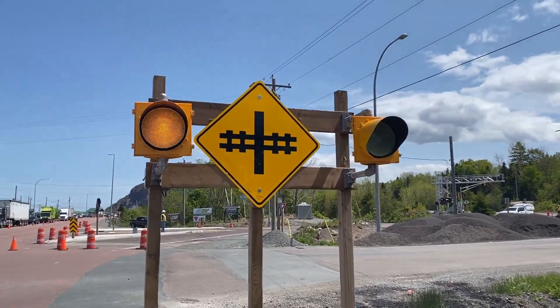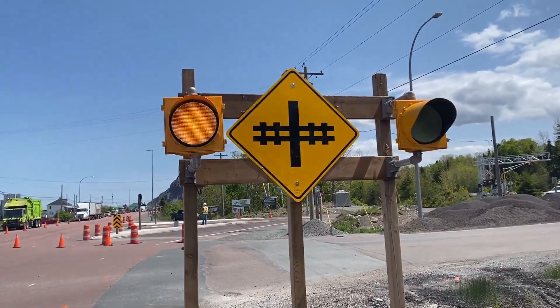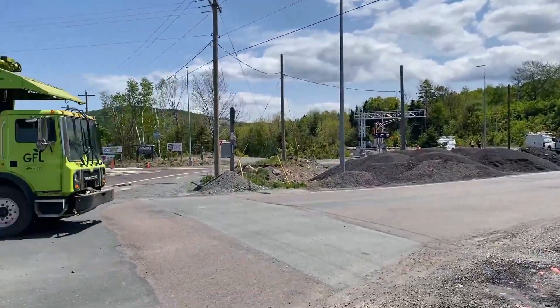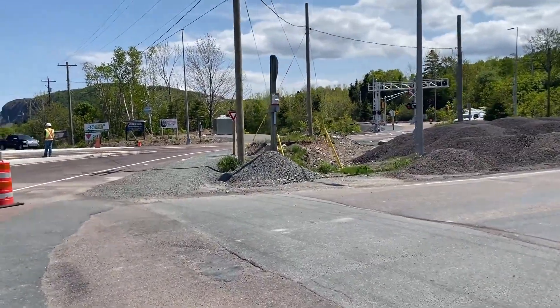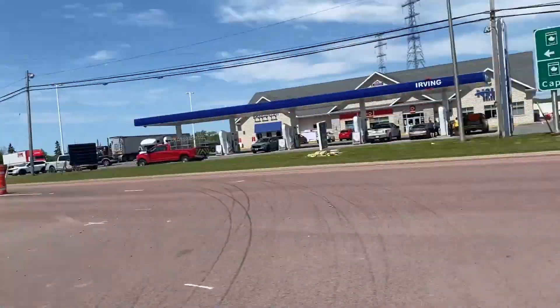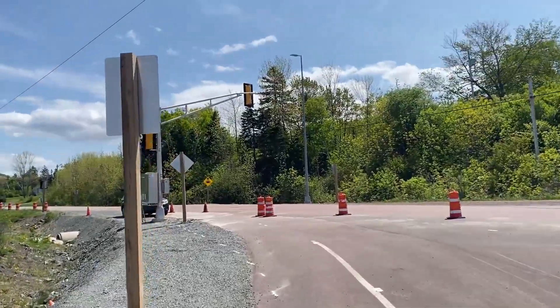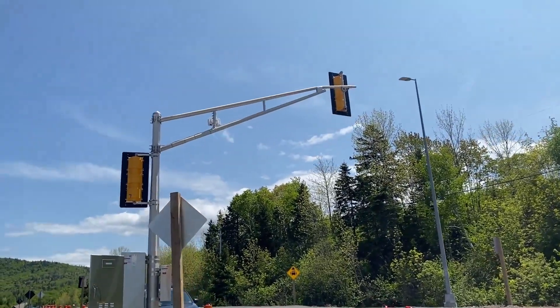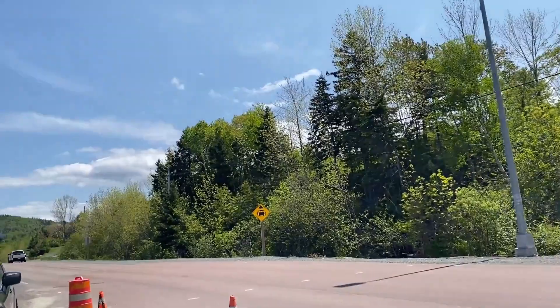That's my load switch 12, which will operate during the train preemption condition and then shuts off when the condition drops. That's for this right turn channel, just because the rail kind of sneaks up on them. Where if you're coming from the left side you can see the lights right away, and it doesn't really require advance warning, but that one's coming off a high-speed slip lane where this road is going to disappear, and it's just warning drivers that the lights are active. Here's the back of the back plates — they're actually black on the back. Typically we go with all yellow, but I have the reflective tape on the front, which is still the correct amount for visibility on approaching vehicles.